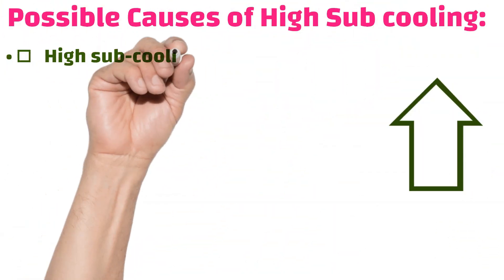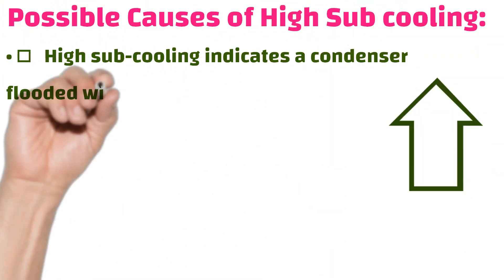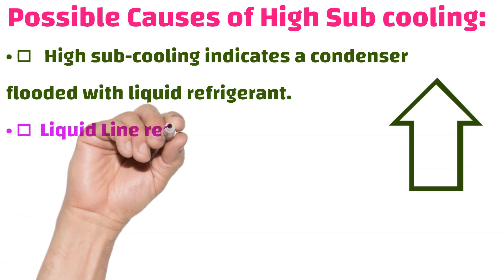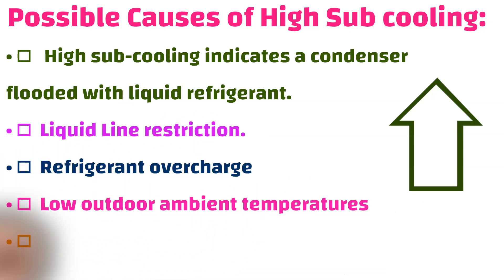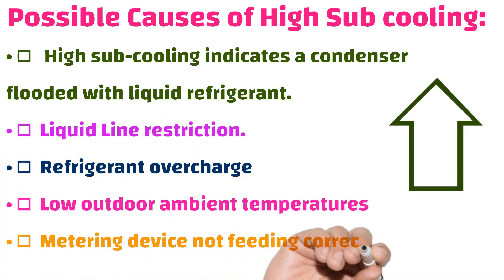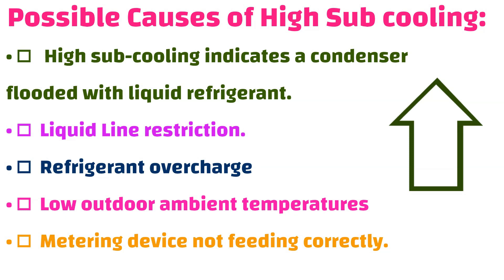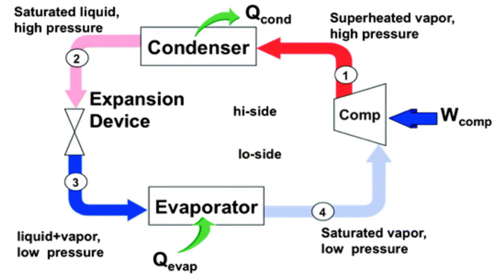Possible causes of high sub-cooling: one, high sub-cooling indicates a condenser flooded with liquid refrigerant; two, liquid line restriction; three, refrigerant overcharge; four, low outdoor ambient temperatures; five, metering device not feeding correctly.